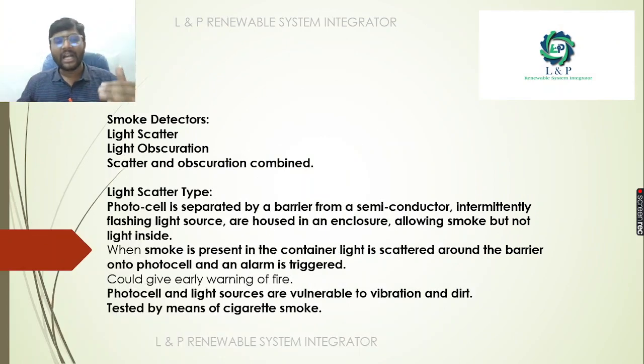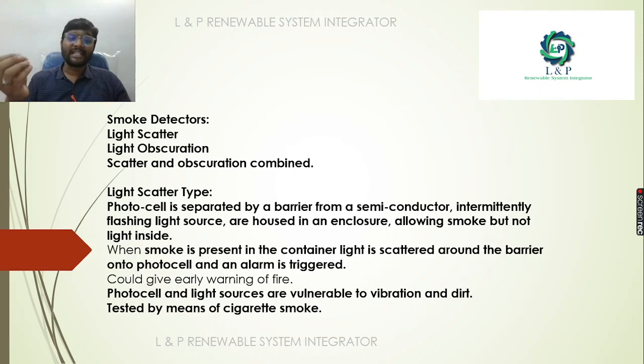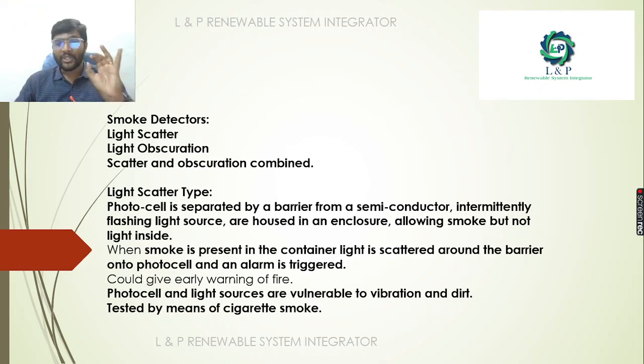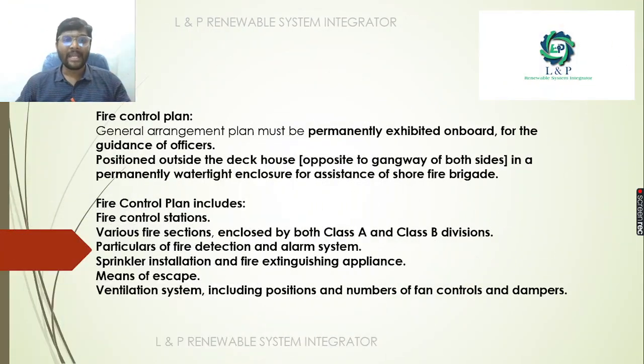Next, if you are going into smoke detectors, there are light scattering and light obstruction types. Next, the light scattering type. The photocell is separated by a barrier from a semiconductor light source. Flashing light sources are housed inside enclosures, allowing the smoke but not the light inside. When smoke is present in the container, light is scattered around the barrier onto the photocell and the alarm is triggered. Photocells and light sources are vulnerable to vibration and dirt, so tests must be done using cigarette smoke also.